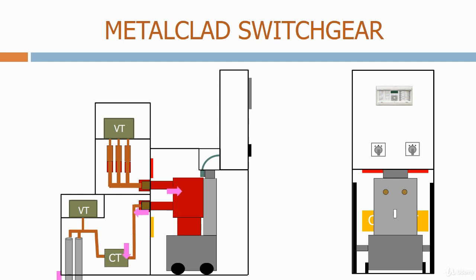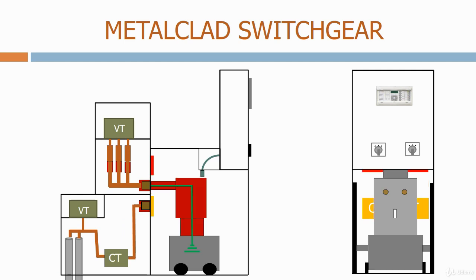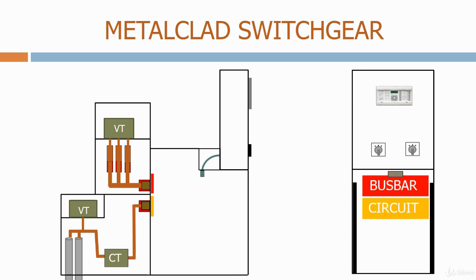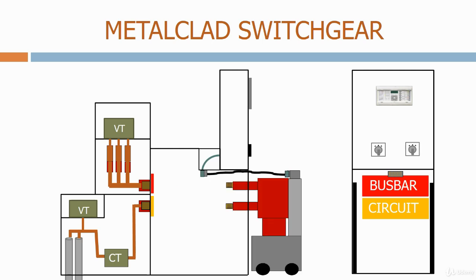Most Metalclad switchgear designs have different types of trucks. One option is a busbar grounding truck. When this is inserted into the housing, it grounds the bus bars. Obviously, before you can do this, all of the sources of supply to the busbar need to have been withdrawn. Another option we can provide whilst testing the circuit breaker is what's called an umbilical cord. This connects the secondary terminals of the enclosure and the secondary terminals of the truck, and allows the truck to be opened and closed when it's outside the enclosure.